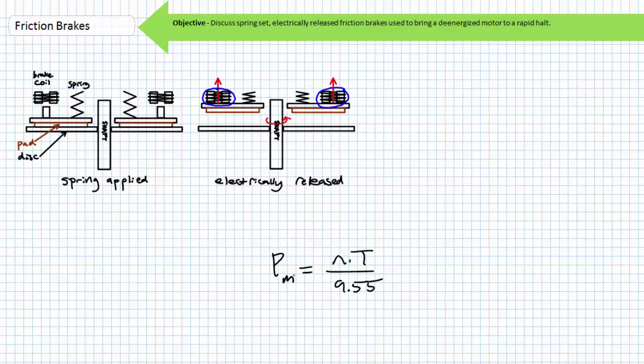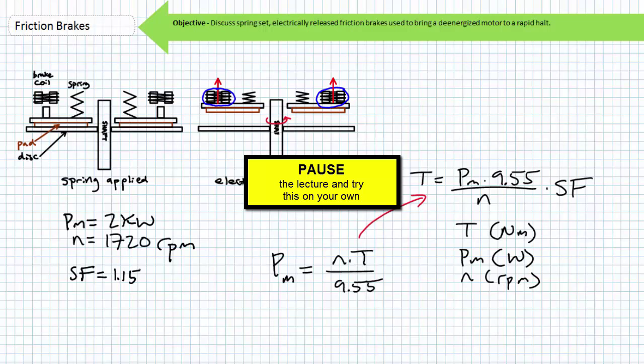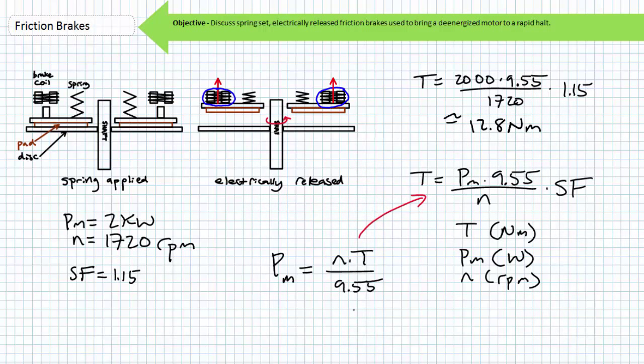As previously mentioned, friction brakes are rated according to the braking torque, which is ordinarily equal to or greater than the full load torque of the motor it is intended to stop. If the full load torque of the motor is not explicitly stated in the motor nameplate, it can be determined using a derivation of the mechanical power formula discussed extensively in the Mechanical Power, Torque, and Rotational Speed lecture available at the Big Bad Tech Channel. This time incorporating a dimensionless service factor figure that ensures the brake can do the job. Note torque is in units of Newton meters, mechanical power is in units of watts, rotational speed is in units of RPM, and the constant 9.55 is a necessary unit conversion. For example, consider a 2 kilowatt motor with a rated speed of 1720 RPM. What is the braking torque necessary to stop this motor if the brake is to incorporate a 1.15 service factor? Pause the lecture and try this on your own. Substituting the necessary values and accounting for proper units, we find that the brake should be able to supply at least 12.8-ish Newton meters of counter torque if it is to do the job.